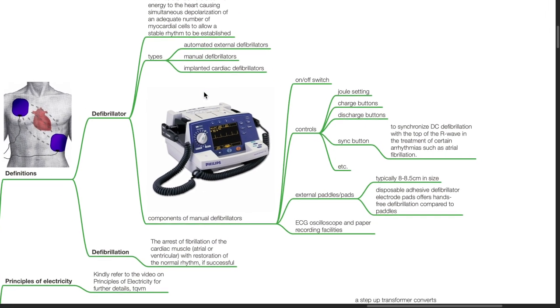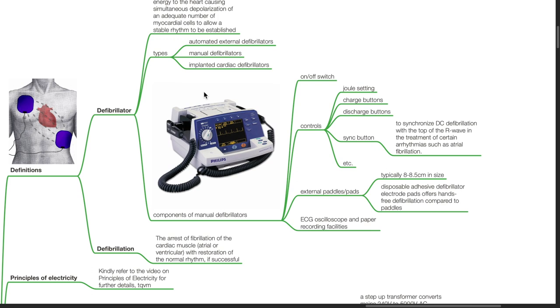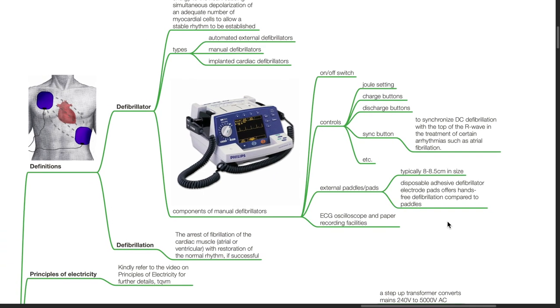Components of manual defibrillators include an on-off switch, controls for joule setting, charge buttons, discharge buttons, sync button, etc. External paddles or pads, typically 8 to 8.5 cm in size. Disposable adhesive defibrillator electrode pads offer hands-free defibrillation compared to paddles, ECG oscilloscope, and paper recording facilities.